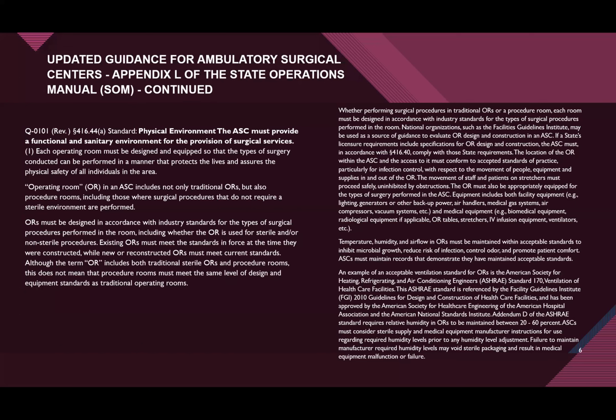We have used non-flammable anesthetic agents as long as I have been in healthcare. And someone said, well, why can't we have the humidity down to 20%? And CMS said, go for it. And then manufacturers of equipment said, oh, we did not test our equipment down to 20%. And we require that you store these products and equipment between 30 and 60%.